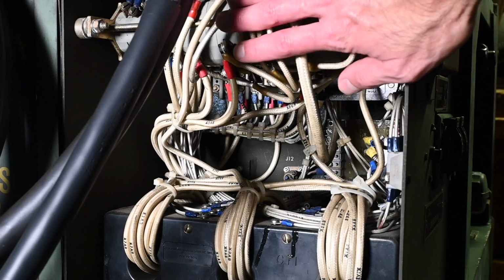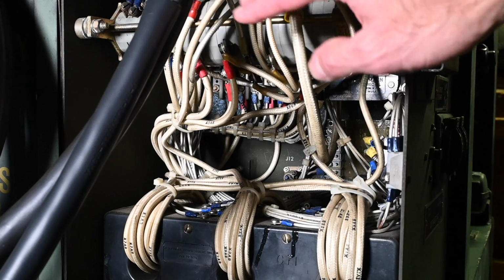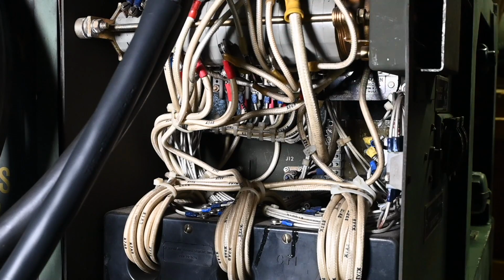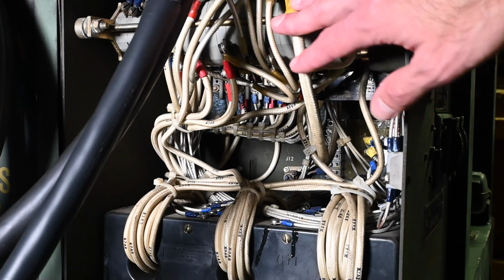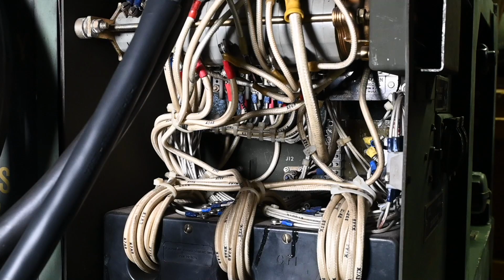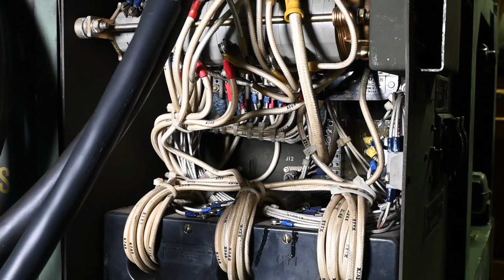So with this rotary switch up here, there's a knob on the front panel. This switch can be set to 3 different types of outputs, and it is only to be moved when the generator is not running, of course. So the main outputs can be 120 volts single phase, 120/240 volt single phase, or 120/208 volt three phase. And because this generator set does 3-phase output, that's why we see these 3 groups of wires down here. Now there's actually a high voltage range that can be configured on 12-wire generators, but this generator set doesn't allow for that.